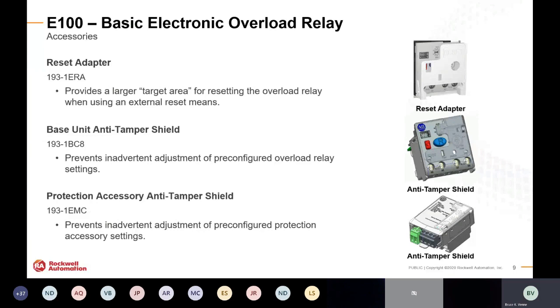So the reset adapter is pretty self-explanatory. It's a small plastic piece that fits over the top of the overload, which provides a larger target area for resetting the overload relay. If this is being used in, say, an industrial control panel or an MCC that has a manual reset button on the front of the door that pushes a plunger, then that plunger can actually hit this reset adapter versus trying to align it very specifically with the target area of a smaller button. Then we have the base unit anti-tamper shield. Again, once the overload is configured from the factory or in the field, you can install this anti-tamper shield to prevent any other inadvertent adjustments in the future of that overload so that nobody can tamper with the device settings.